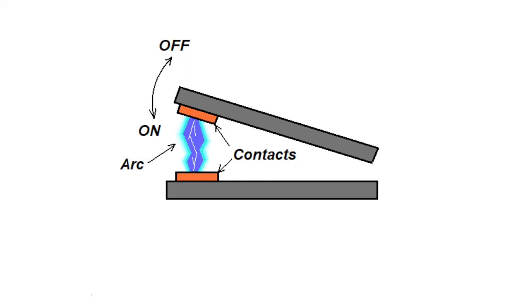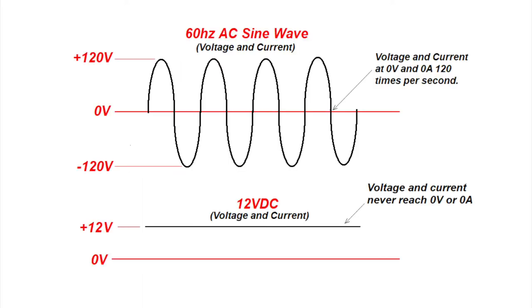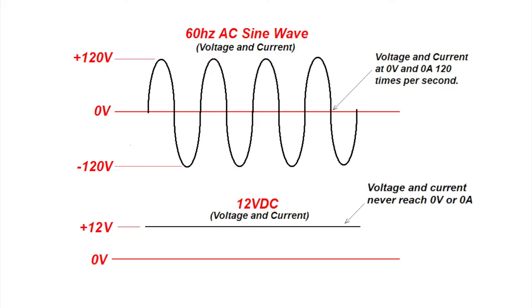In AC power the voltage and current will be at zero 120 times a second due to the 60 hertz power line frequency. The passing through zero volts actually aids in lowering both the arcing potential and duration. In contrast, in a DC power line the current is constant so it does not aid in this arc suppression. In other words, the voltage is removed 120 times a second in AC which helps the switch open and close. In DC the current is constant so that arc will never go away until the switch contacts go far enough apart that the arcing no longer occurs.